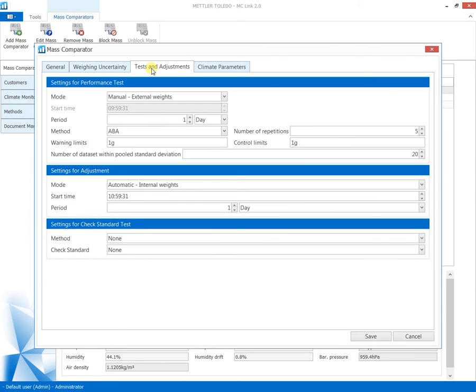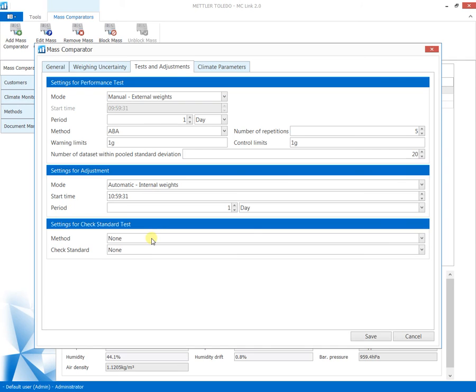In the tests and adjustments section, time scheduled testing and adjustment of the comparator is defined. Select from fully automatic repeatability testing with internal weights or manual with reference weights. To adjust the sensitivity of the comparator, select automatic with internal weights or manual with reference weights.